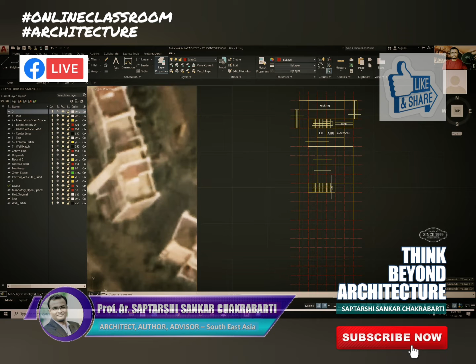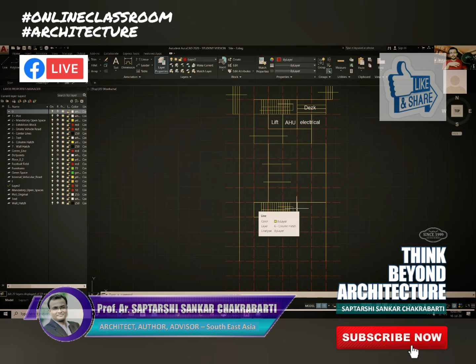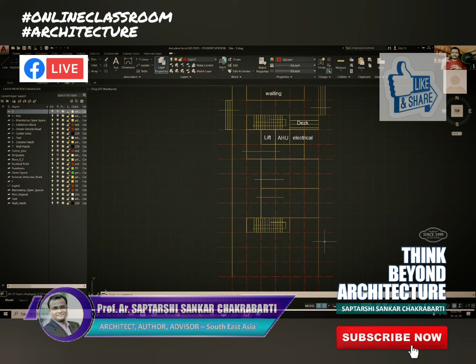And another thing, sir, was that the emergency staircase, we have to provide at least one emergency staircase that is facing towards the external wall of the building, right? Yes, it should be getting direct access from the external facade. Ideally, it should be outside the building, completely open to the sky, completely open to natural ventilation, so that there is no smoke accumulation in it. I think you can do it actually, because your building is not that high, and secondly, if you have an exposed staircase, it looks good from the outside, right? And the third point is, if you have an exposed staircase, it's the best option that you can have in a public building.